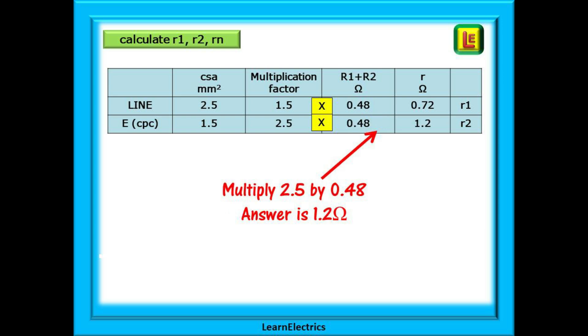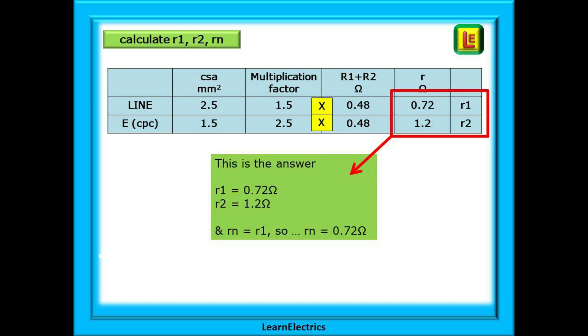Now, the CPC row. Multiply 2.5 by the same 0.48, and we have an end-to-end resistance of 1.2 ohms for little R2. And that is it.